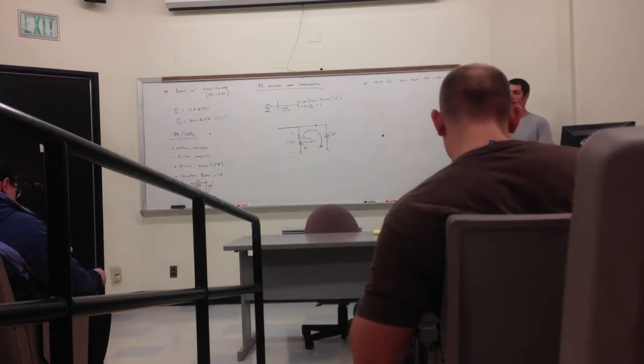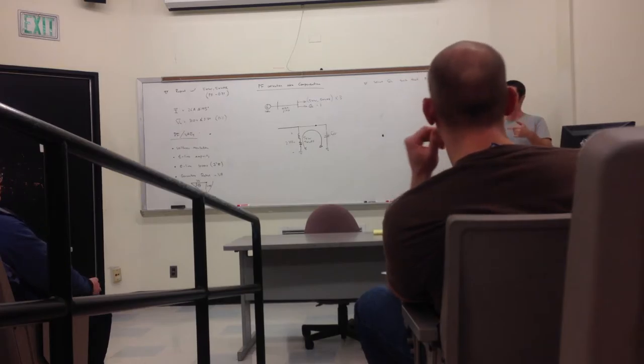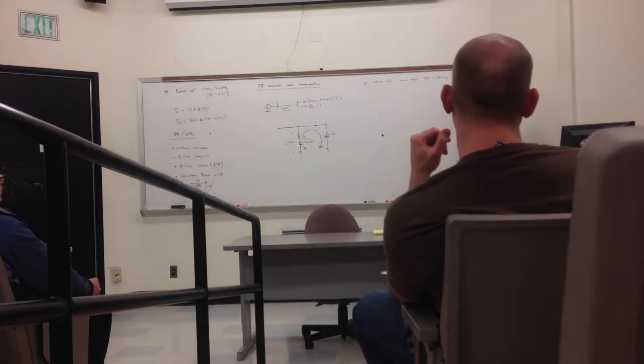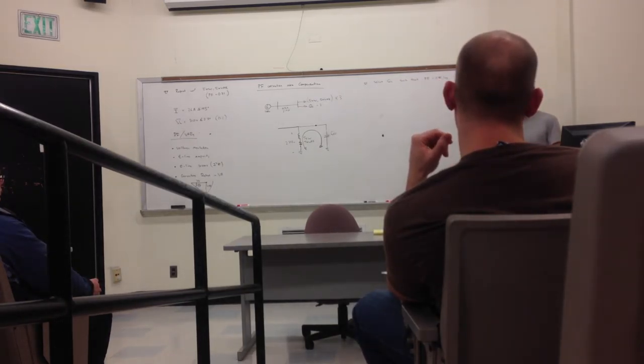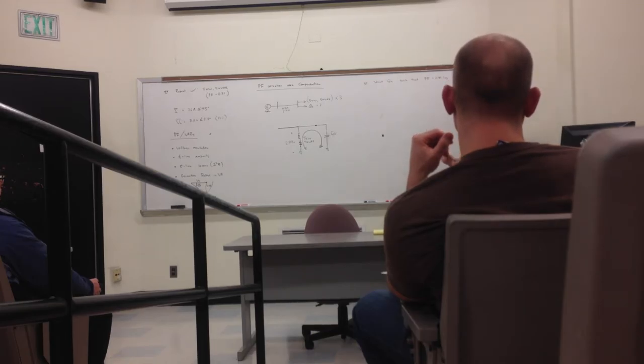So we're going to shoot for 0.85. If you get above that, the utility is going to stop charging us. Again, it gives us some breathing room to get down to 0.75 on occasion. So we'll go to 0.85, get rid of the penalty, and not buy any more capacitors than needed.